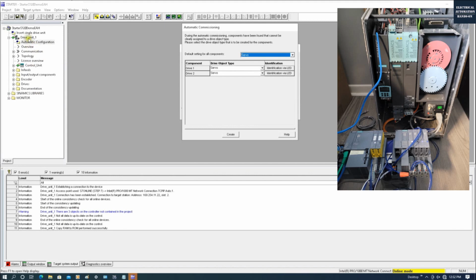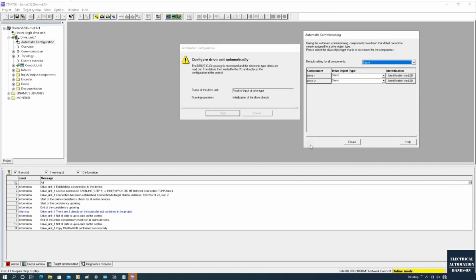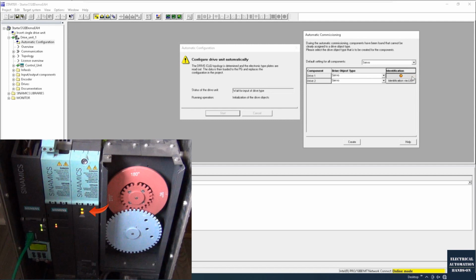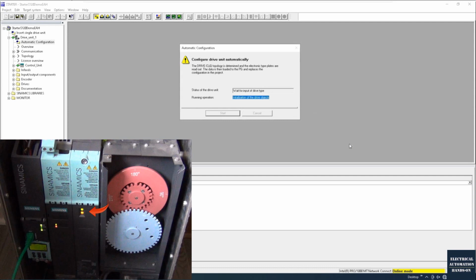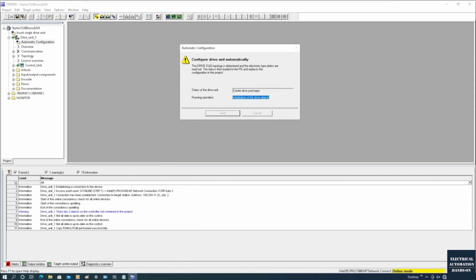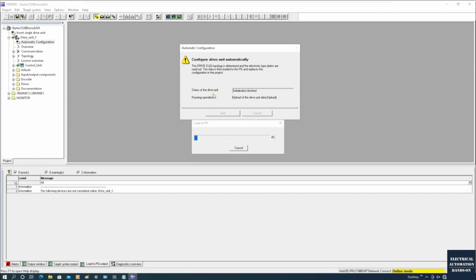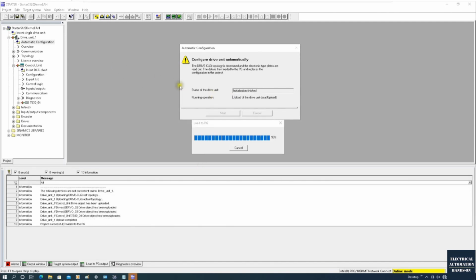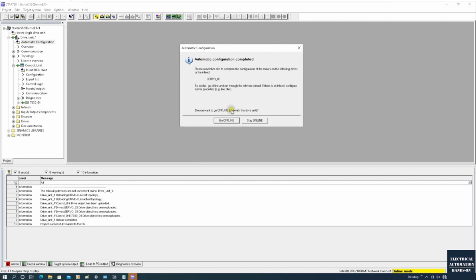And we can see the system automatically detects we have 2 servo drives in the system. And we can click this identification with the LED. And we can identify the motor module. We'll try to configure. Okay, let's click this create. And after this, we can see the drive area. The system can identify the drive area. It should identify 2 servo motors. Okay, we can see it's uploading the drive unit. And the system notifies us that for servo 3, we need to manually configure something.